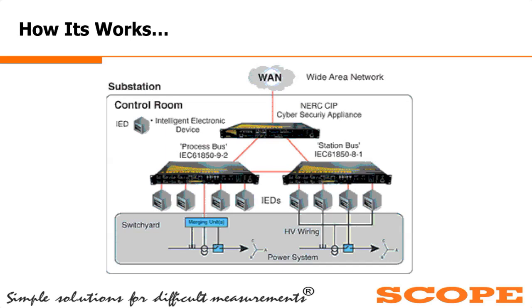So for that, we normally use intermediary switches, where all those digital devices terminate, and one end will be connected to your server, which will show you those IEDs. So whenever it comes to digitalization of substations and industries, you require these Ethernet switches, and if multiple networks are involved, you could require routers.